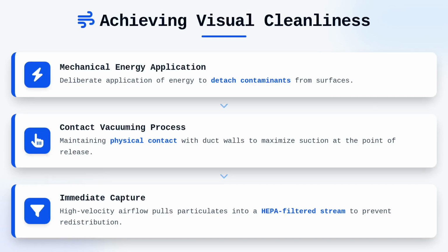The goal is to create a localized zone of high-velocity airflow that pulls dislodged particulates directly into the HEPA-filtered vacuum stream before they can disperse into the airstream. This direct contact method is the most reliable way to achieve the NADCA standard for visual cleanliness, as it ensures that particulates are removed rather than simply redistributed within the ventilation network.